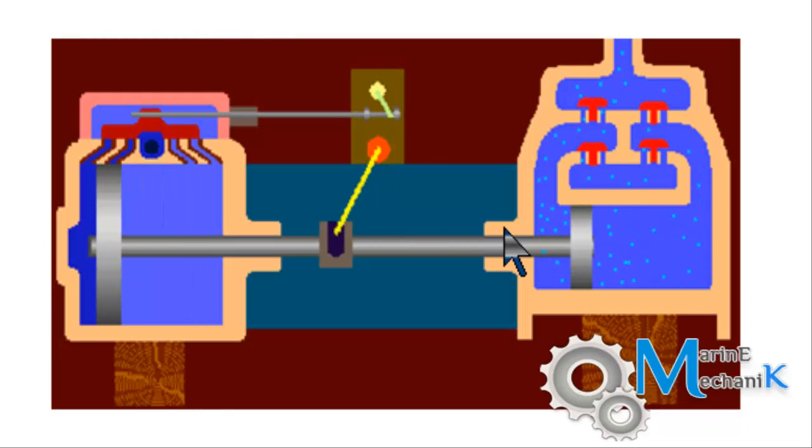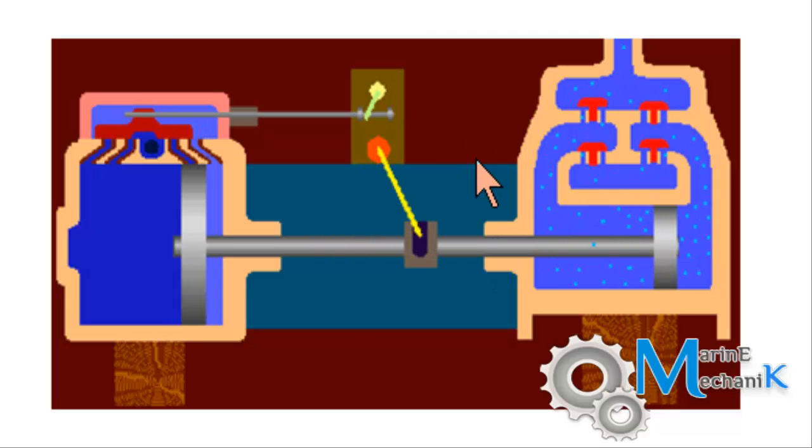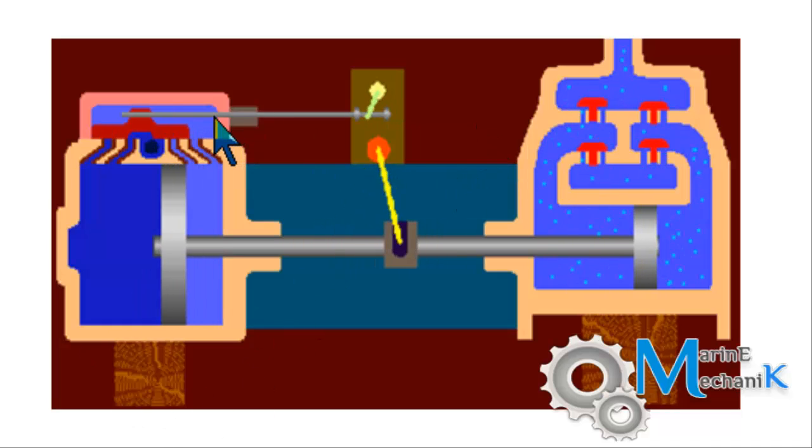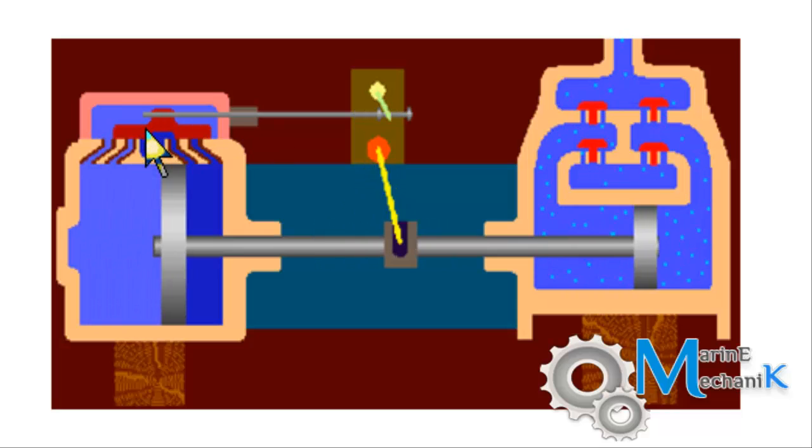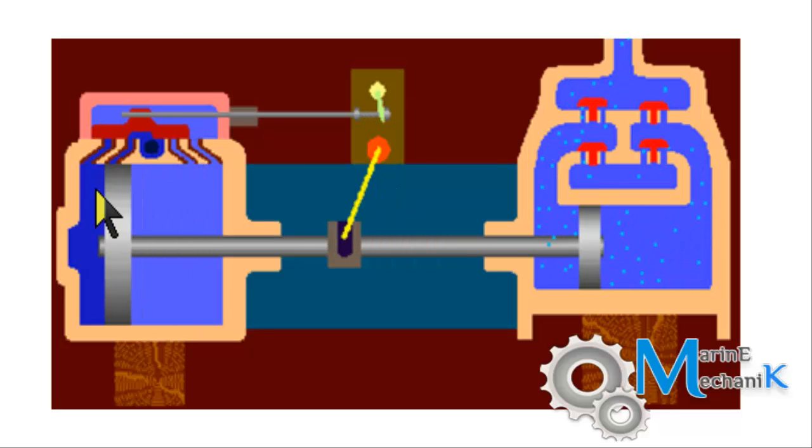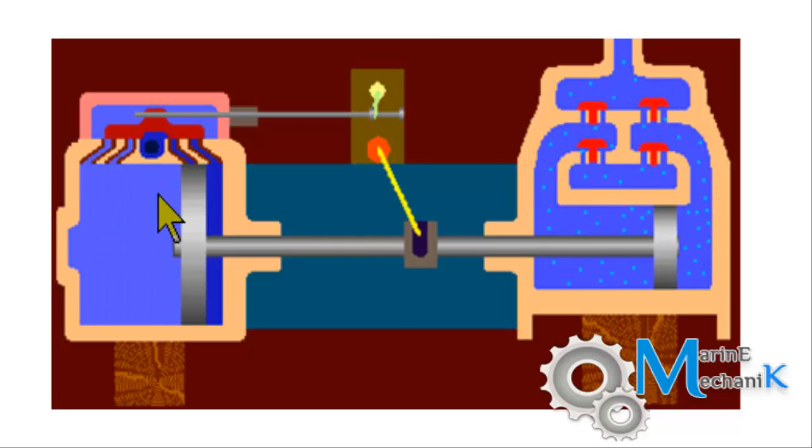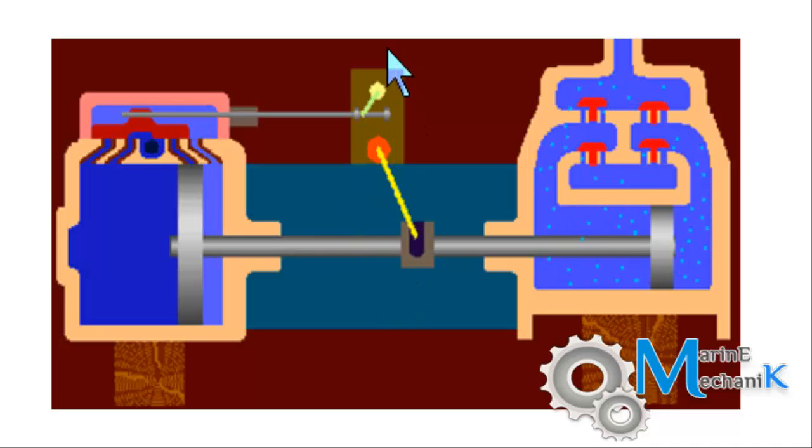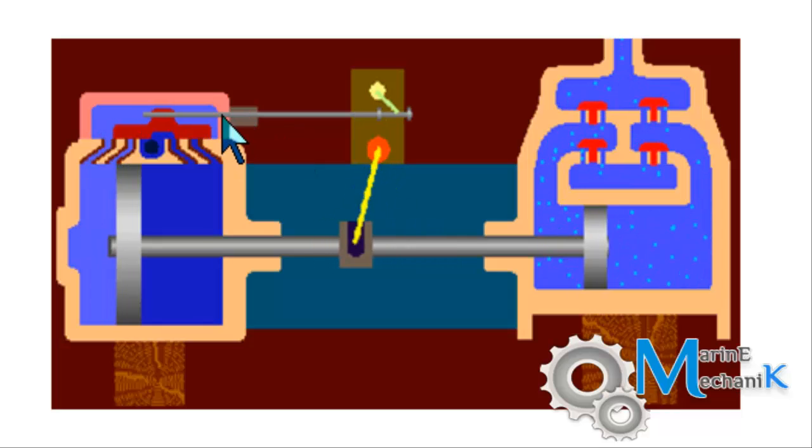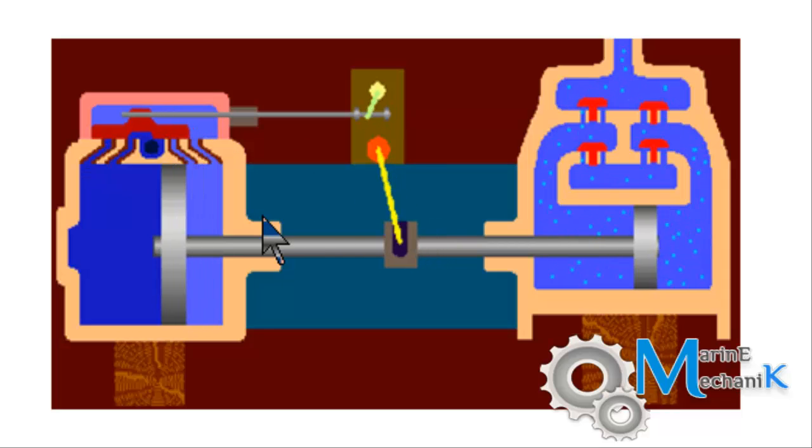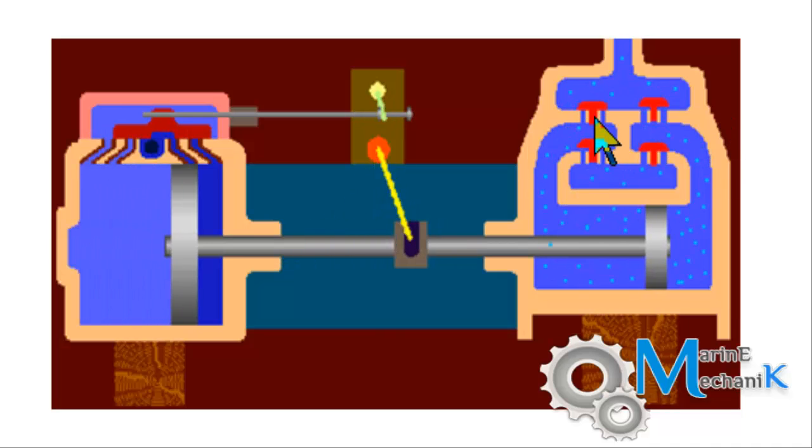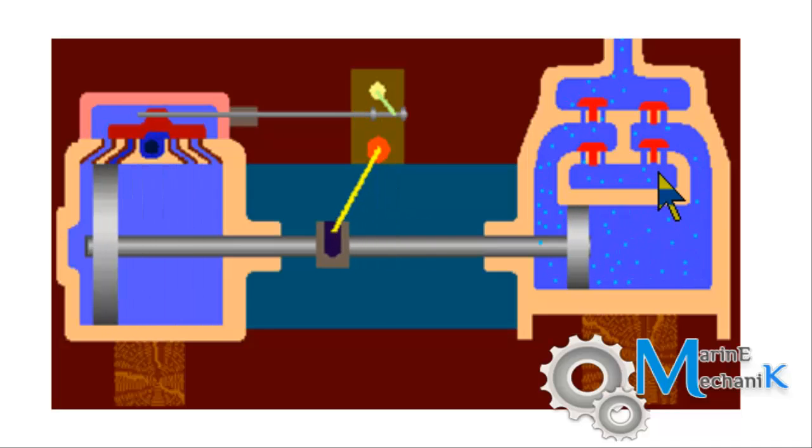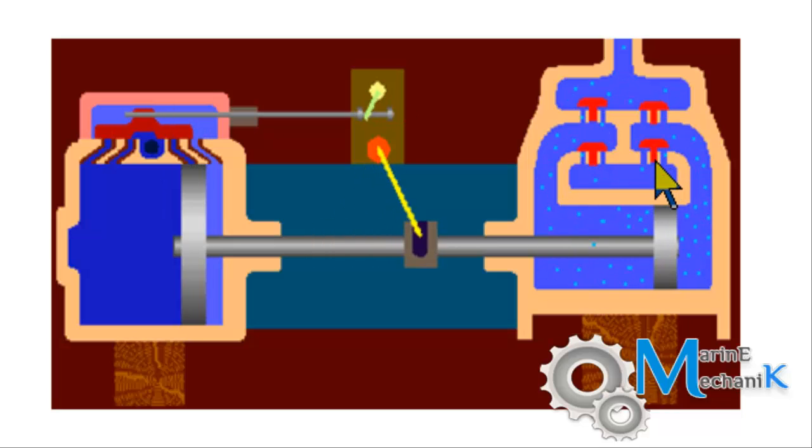That's the steam operated reciprocating bilge pump which you can find it on olden day steam ships. Here is the steam chest where the steam pilot valve controls the inlet and outlet of steam on top of the piston and bottom. This is a double-acting steam piston, and here is the crosshead mechanism which drives the pilot valve over here. Thus the steam is diverted on top and bottom of the system alternately. This is the suction valve chest.